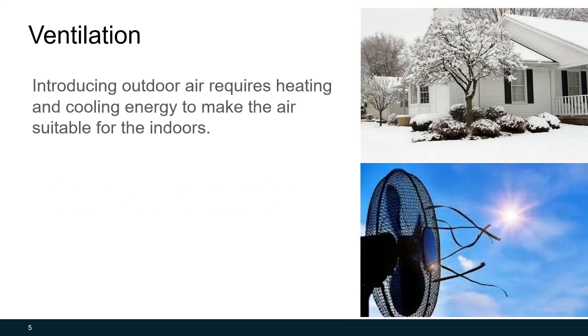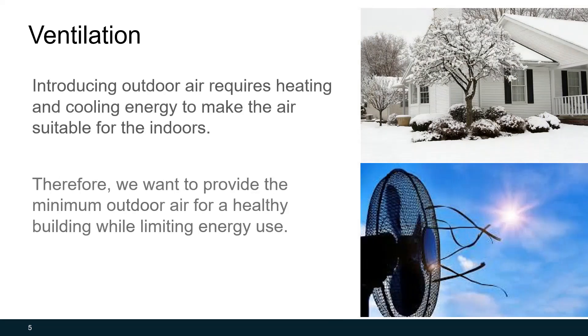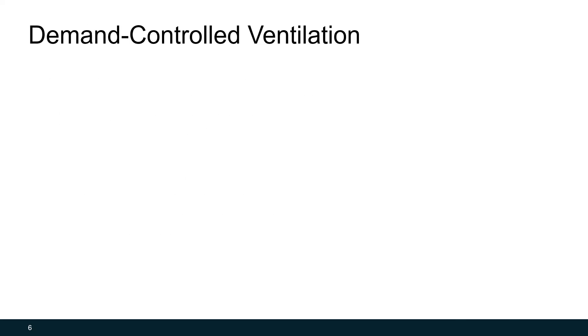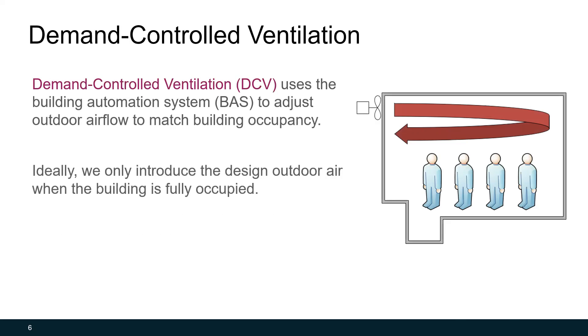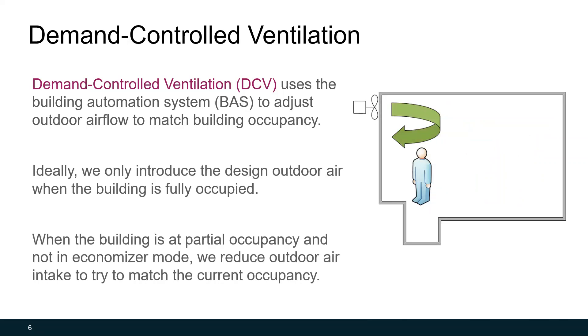However, whenever we bring in outdoor air, we need to either heat the cold air or cool and dehumidify it to make it suitable for the building. Because of that, we don't really want to bring in any more outdoor air during extreme conditions than we need to. So the idea is we want to provide the least amount of outdoor air to save energy, but enough to keep our occupants healthy. Demand-Controlled Ventilation uses the building automation system to adjust outdoor air flow rates automatically to match building occupancy. When the building is partially occupied, we can reduce that airflow and match the number of occupants we have, and therefore save energy.